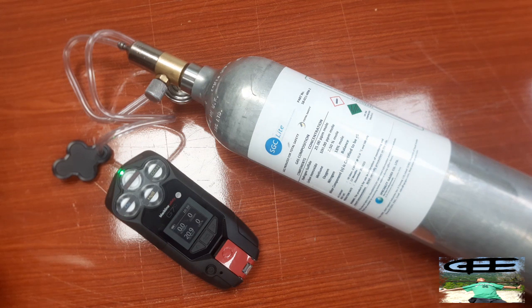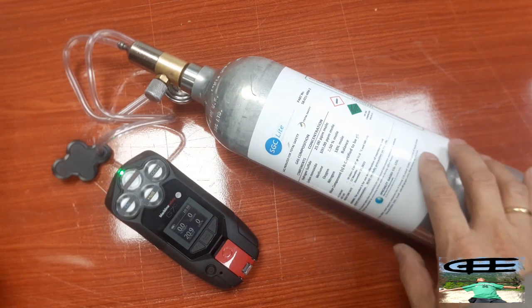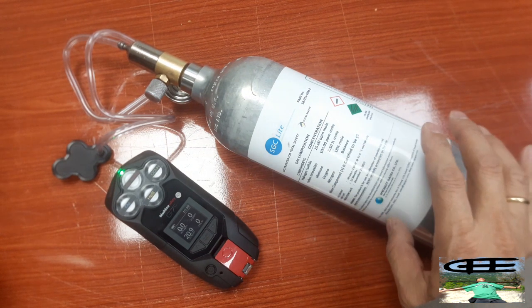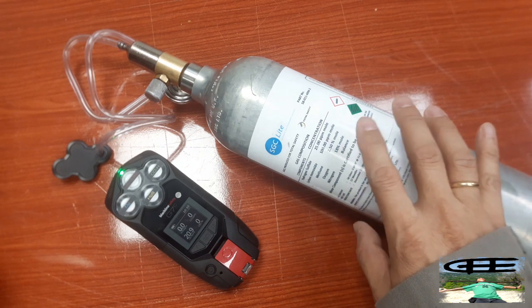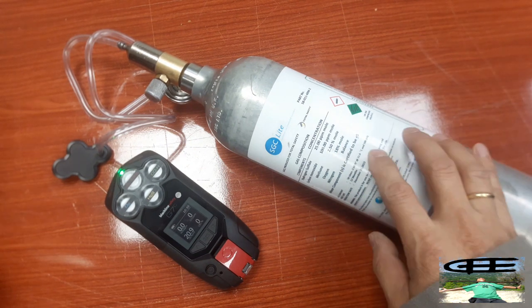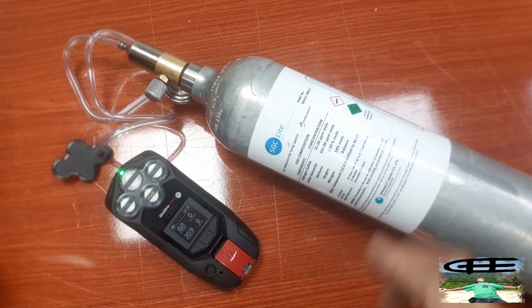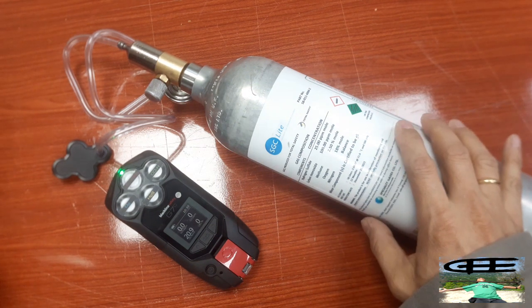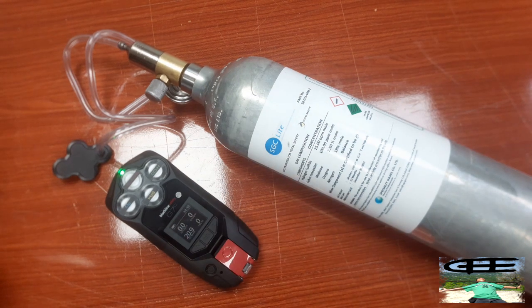All we need to do is have the cylinder gas, which has H2S 25 ppm, CO 100 ppm, methane 2.5% (50% LEL), oxygen 18%, and nitrogen balance. This gas should be matching our G7c unit.